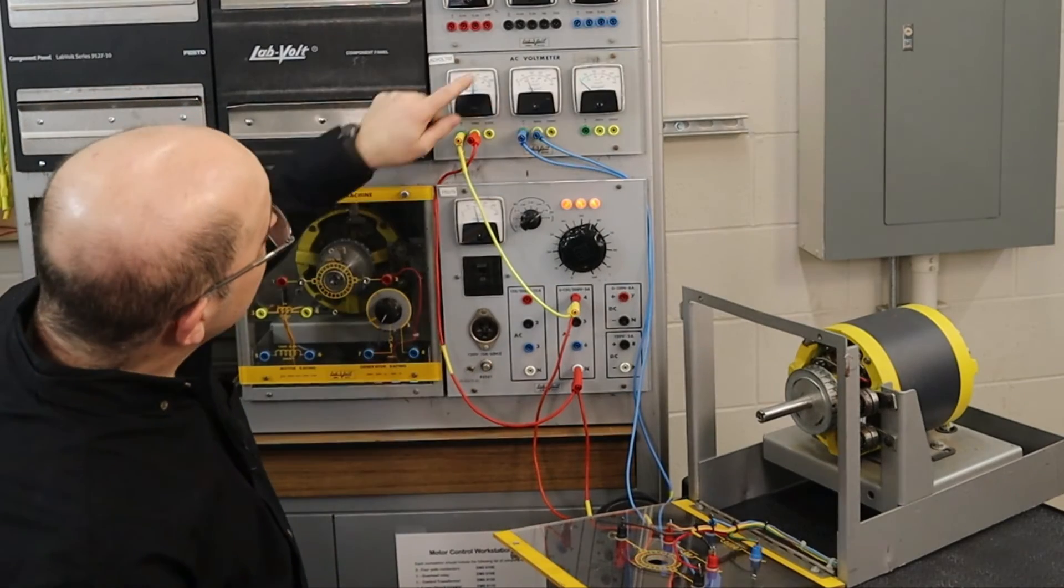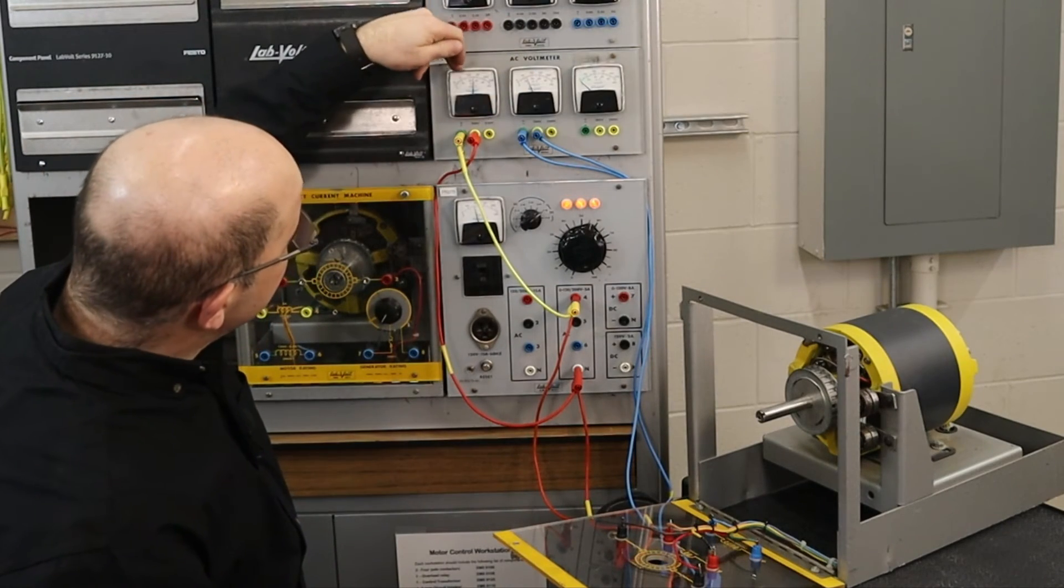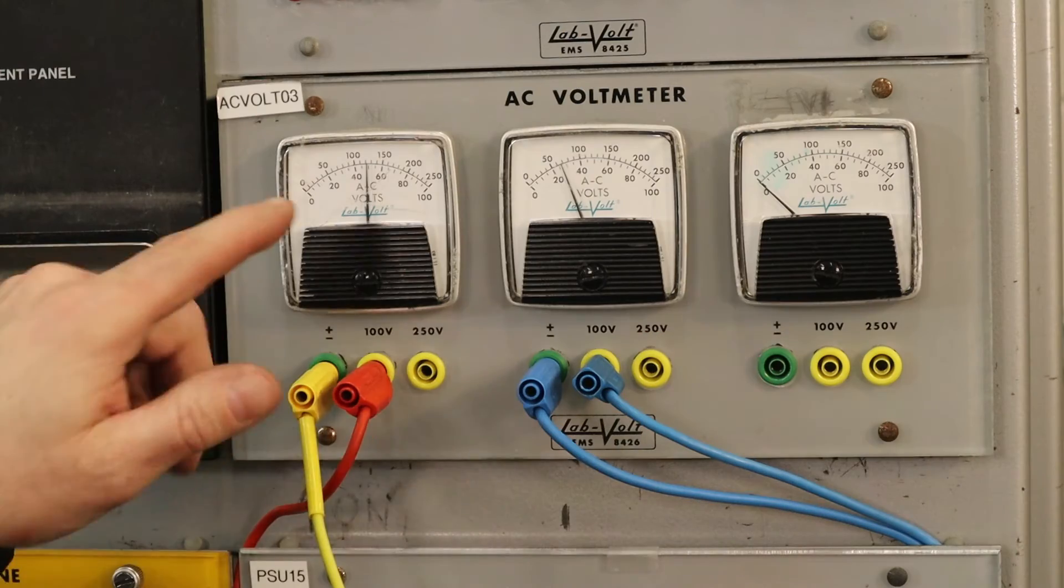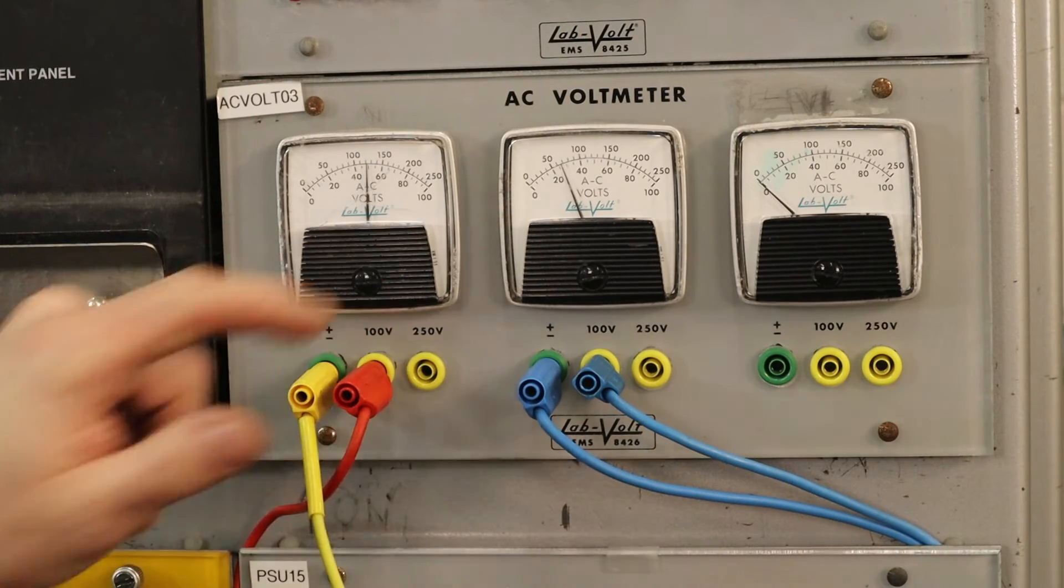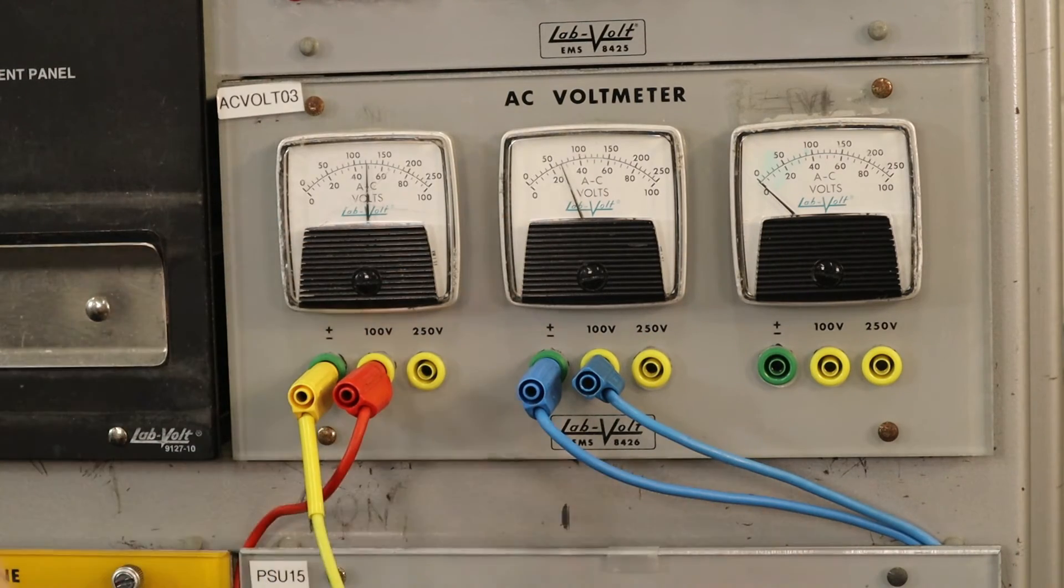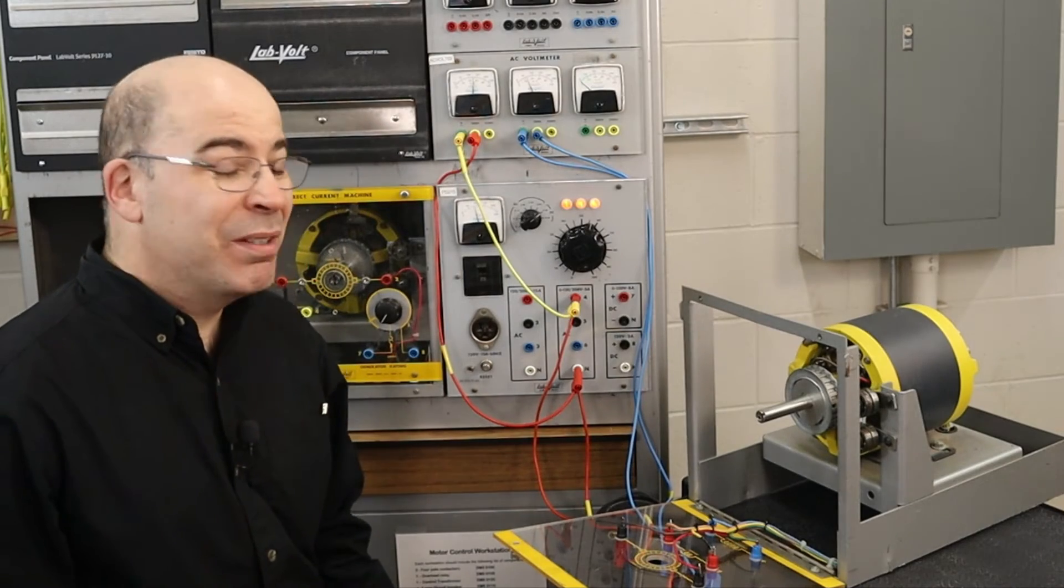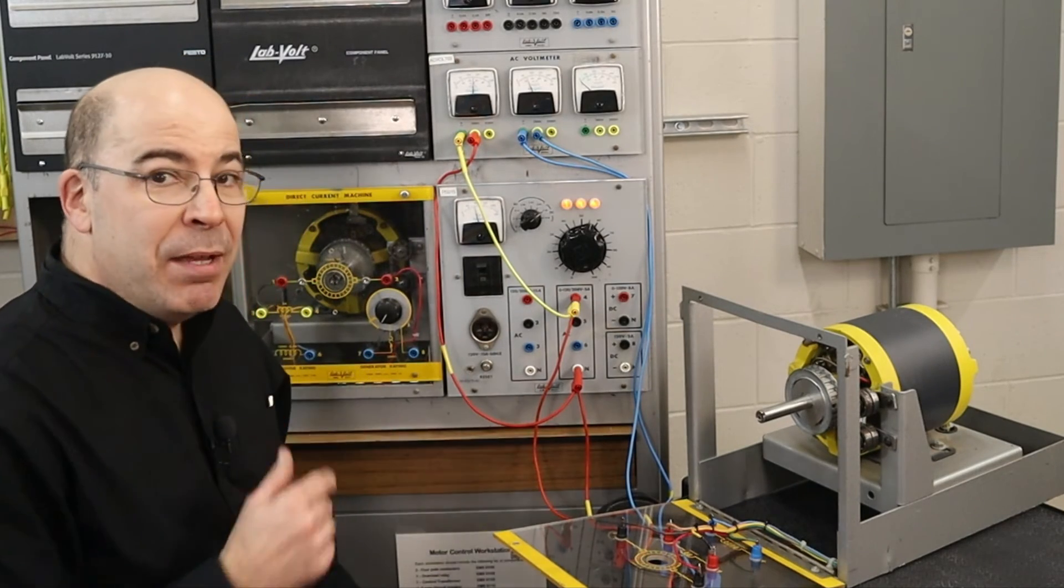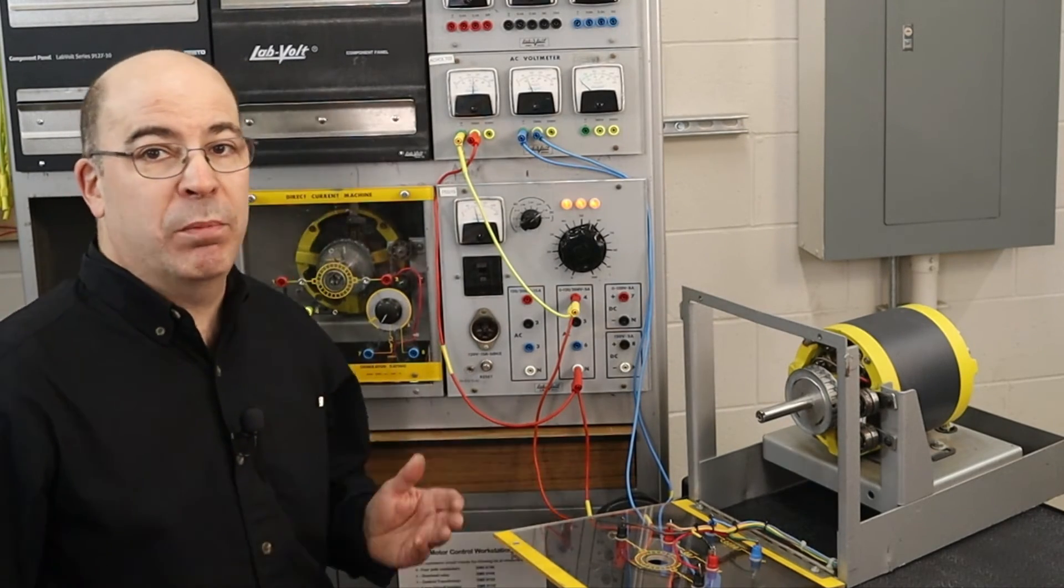Now what we can see is that this is my input, this is the series field, and I'm only reading about 25 volts, roughly half. Now that means that my brushes are not properly set.